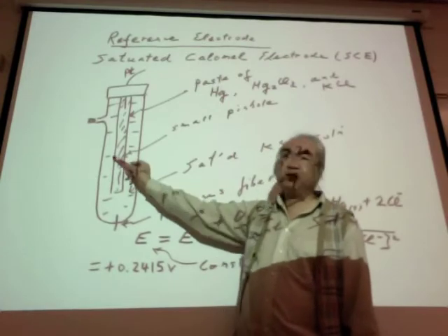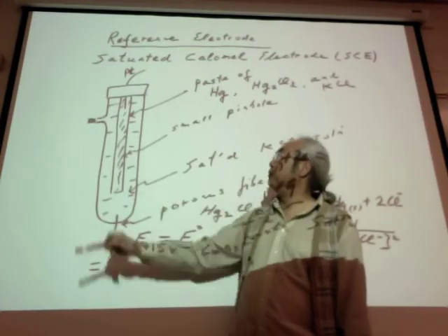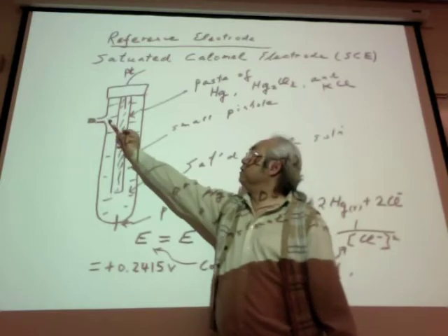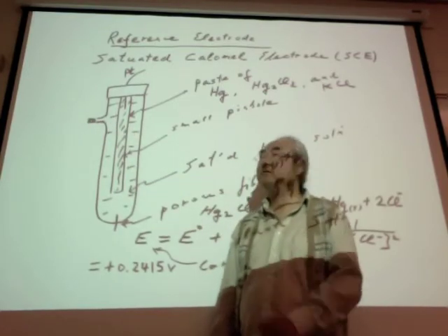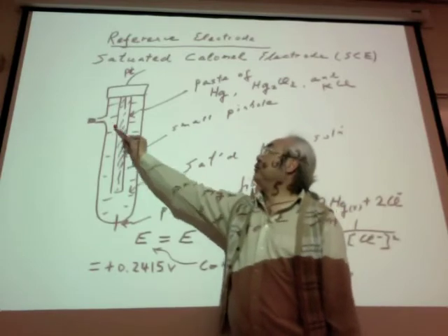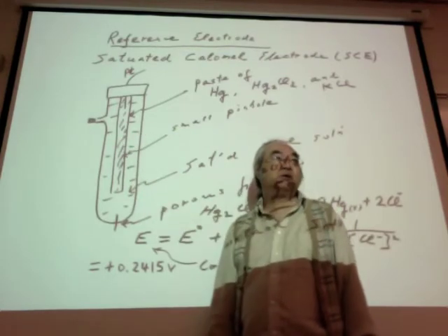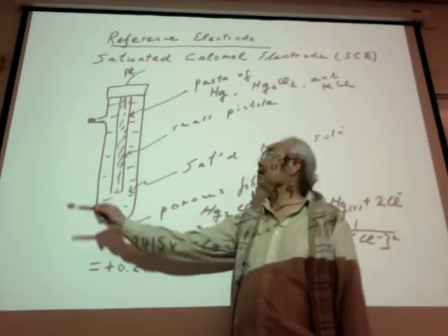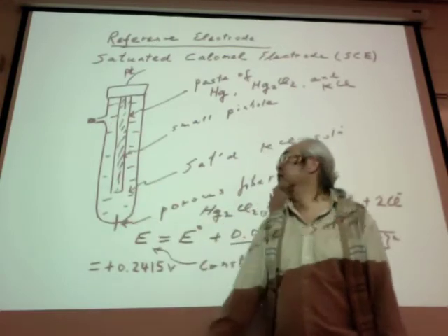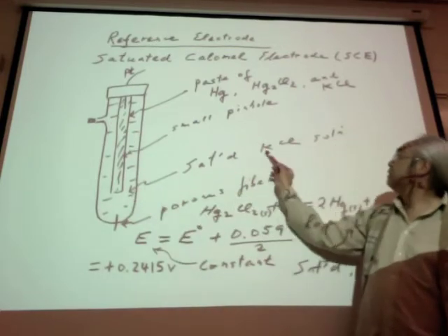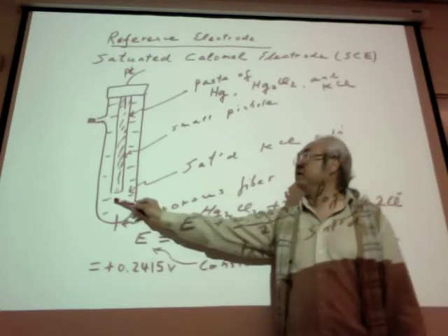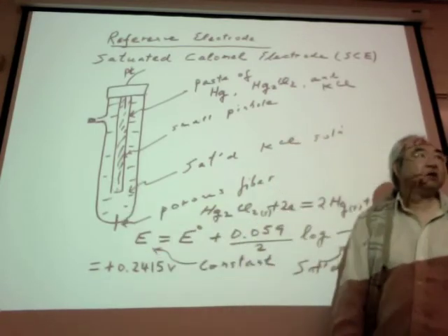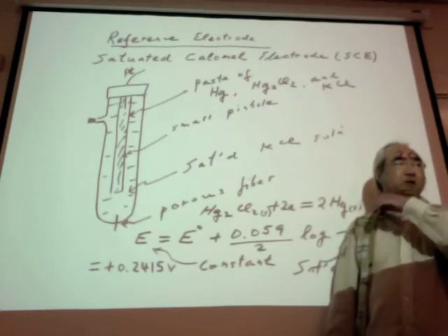It is not just water. Some people think that when there's a hole to fill in a liquid, they put in deionized water. No, that's not it. Or some say let me put in buffer solution. It is not buffer solution. It's KCl. Remember that, because in the real world a lot of people still mistakenly use buffer solution, pH 7.